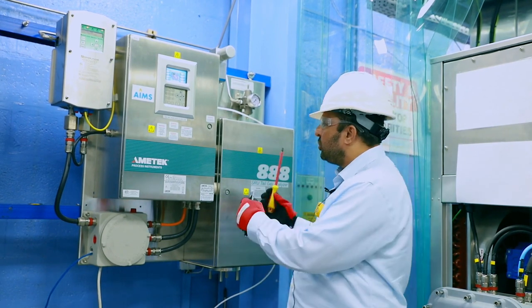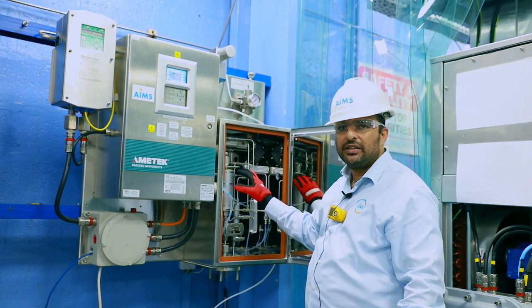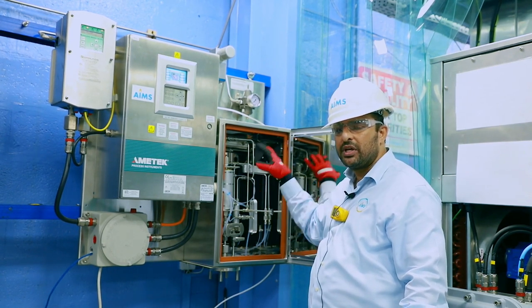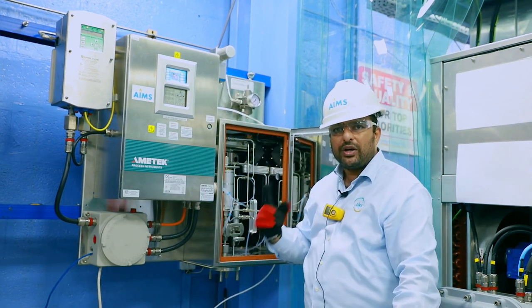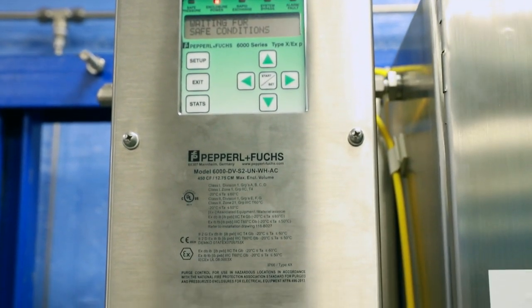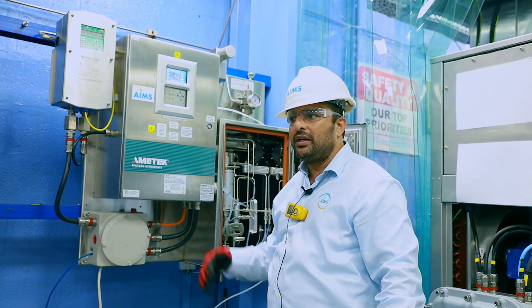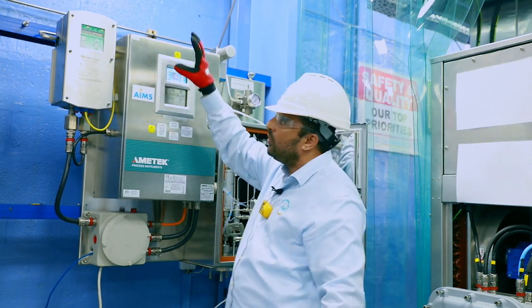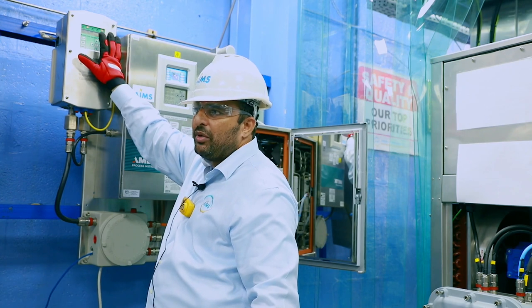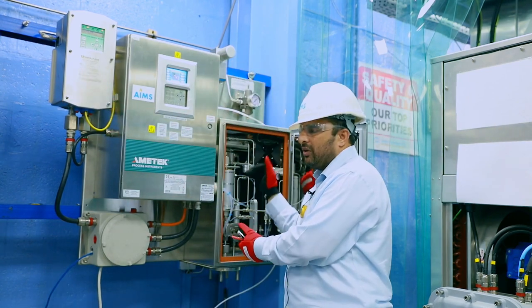Ametek has continued the 888 approach with a heated optical section and an electronics section. For Zone 1 units, there is a purge unit; make sure the purge unit is in bypass mode before opening any enclosure, otherwise it will trip the whole analyzer and may send a fault signal to the control room. The bypass mode is done through the purge controller before opening any enclosure.